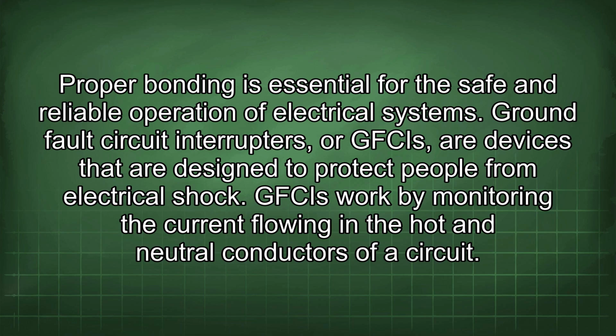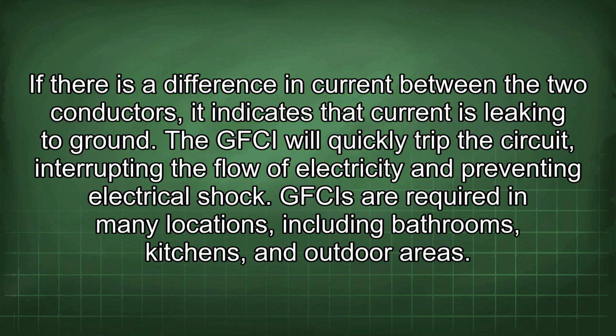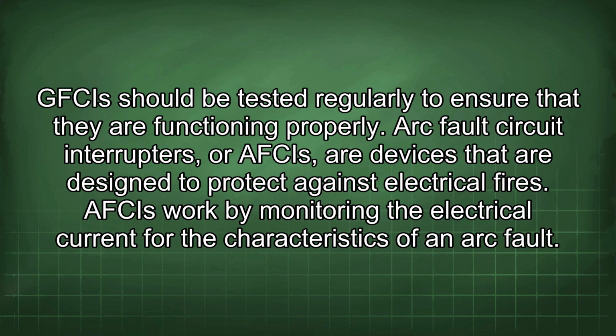Ground fault circuit interrupters, or GFCIs, are devices that are designed to protect people from electrical shock. GFCIs work by monitoring the current flowing in the hot and neutral conductors of a circuit. If there is a difference in current between the two conductors, it indicates that current is leaking to ground. The GFCI will quickly trip the circuit, interrupting the flow of electricity and preventing electrical shock. GFCIs are required in many locations, including bathrooms, kitchens, and outdoor areas. GFCIs should be tested regularly to ensure that they are functioning properly.